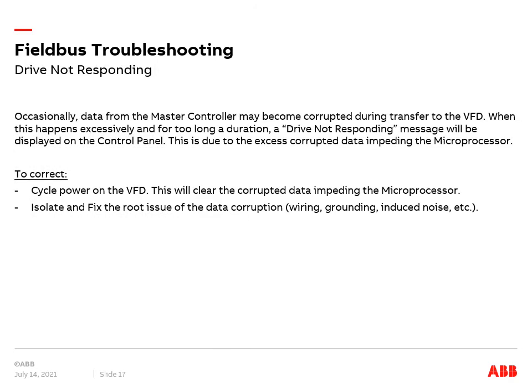Regarding Drive not responding: occasionally, data from the master controller may become corrupted during transfer to the VFD. When this corruption happens excessively and for too long a duration, a Drive not responding message will be displayed on the control panel, due to the excess corrupted data impeding the microprocessor. To correct this issue, cycle power on the VFD to clear the corrupted data. Then isolate and fix the root issue of the data corruption, whether it be wiring, grounding, induced noise, etc.